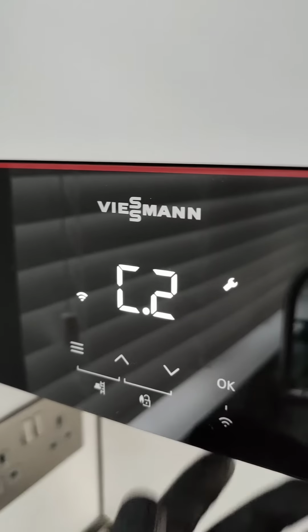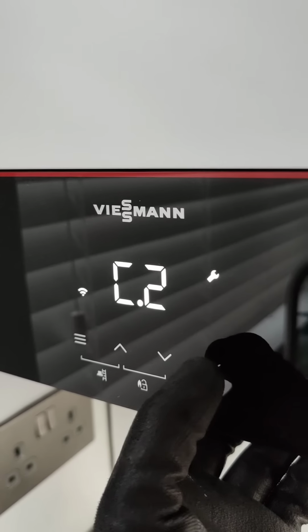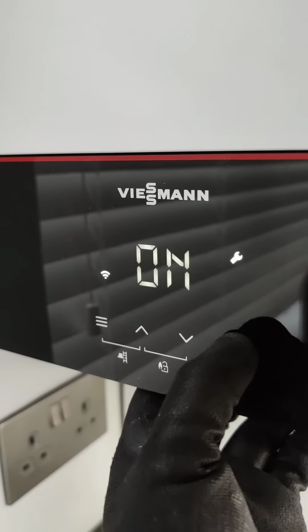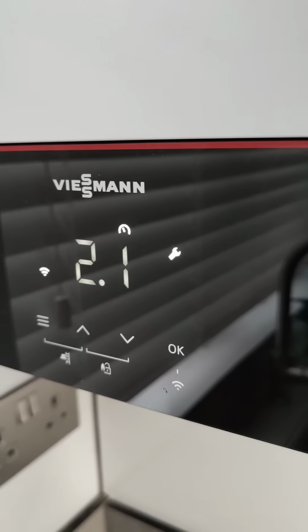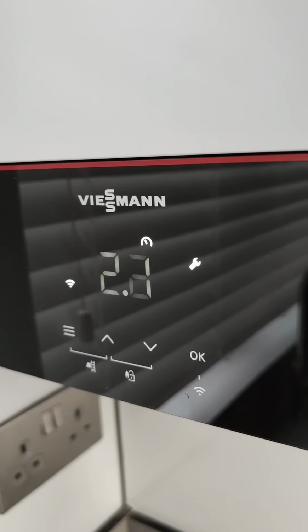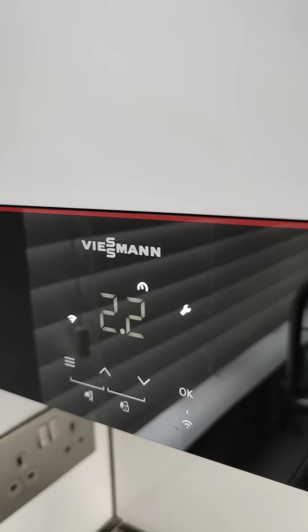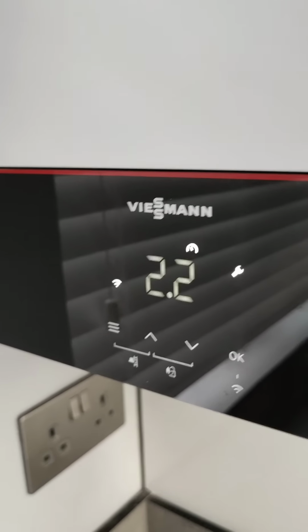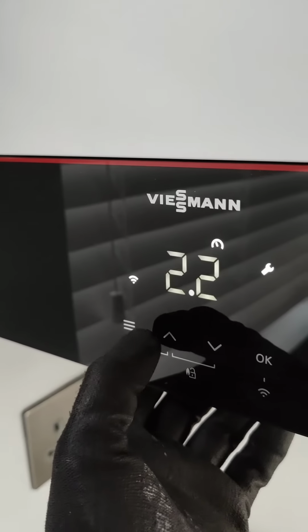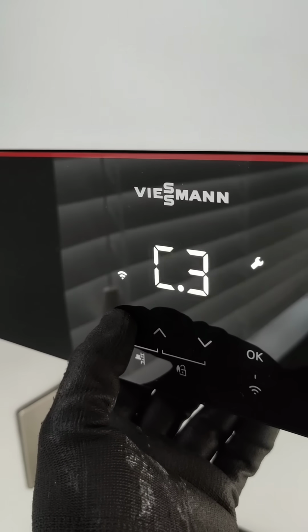Now C2 is the air purge, which will cycle the pump on and off every 30 seconds. So once we fill the system we need to run the air purge. So again we can stick it on or off. Now the pump will run on and off every 30 seconds for 20 minutes. And make sure the automatic air vent is open inside the boiler when we're doing this. So again we can get out of it by holding 4 seconds.